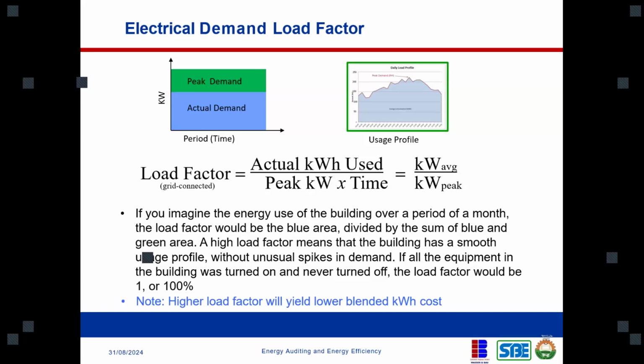So now, this illustration is for grid connected. I've spoken a lot about generator, yes, but this illustration is for grid connected, and this is presented in a scenario where you are being charged demand cost. I mean, where you pay for demand charge. Okay, so if you pay for demand charge, for example, if you're living in America and you have a demand charge component in your electricity tariff, how do you calculate that, and how are you able to manage that? Now, your load factor, which actually is what translates into your demand, is the actual kilowatt hour, this is energy, actual kilowatt hour use divided by your peak times time. Okay, so this is how you calculate your load factor.